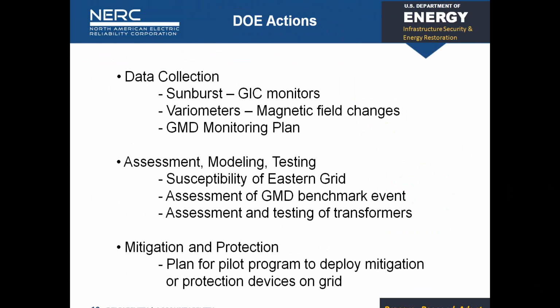some looks at what you can do to mitigate as well. I mentioned instrumentation of transformers. It's really important to see if a problem's, quote, brewing in your transformers, so you can take action to prevent damage. Some of that really needs to be done as the transformer is built and designed. It's hard to go in and put an instrument inside your transformer to start measuring things if you've already built it.